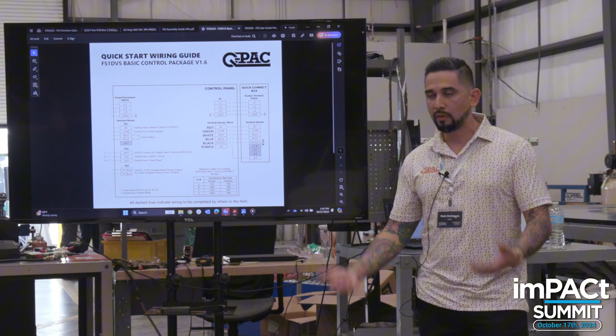And okay, so alarms. These are your basic alarms. You have safety circuit. It tells you exactly what it is. You'll call, be like, I got a 1000 alarm safety circuit. That means your 24 volts to DI1 has been broken. It's open, your safety's tripped, or possibly a fuse blown. We'd help you troubleshoot that if you could not figure out that your safety is closed, but you're still not getting that safety circuit to close.